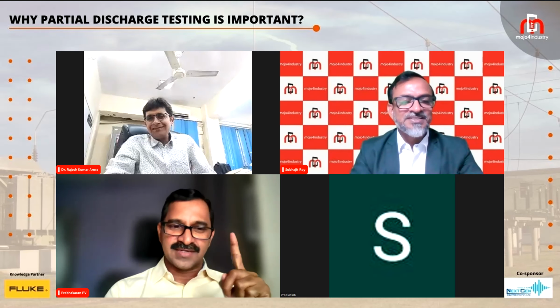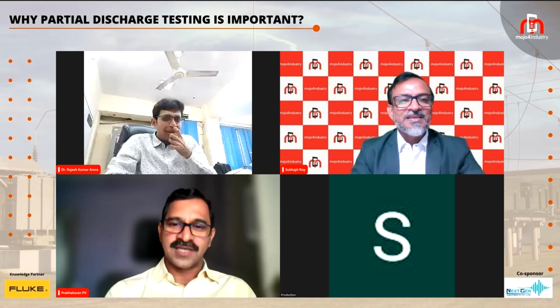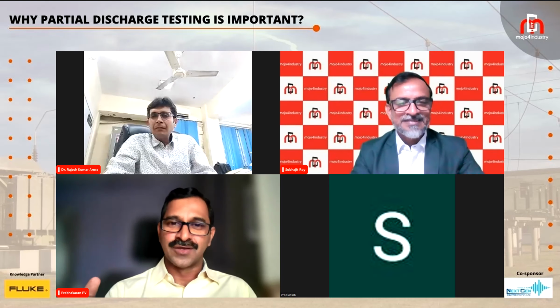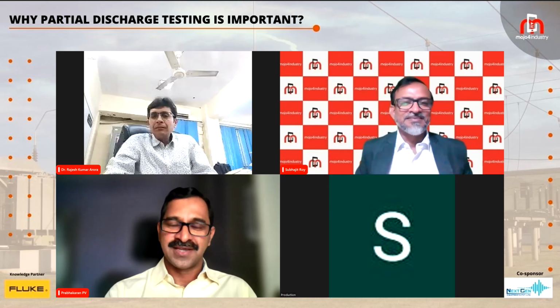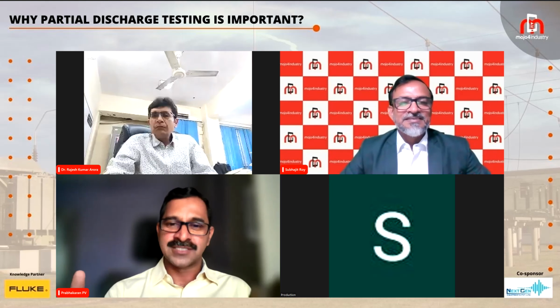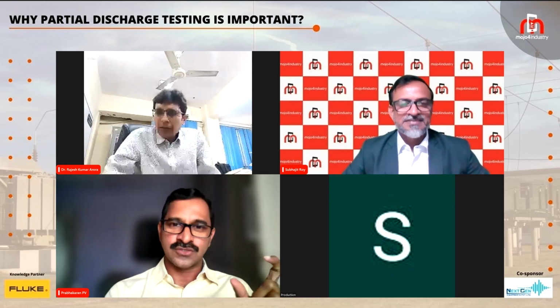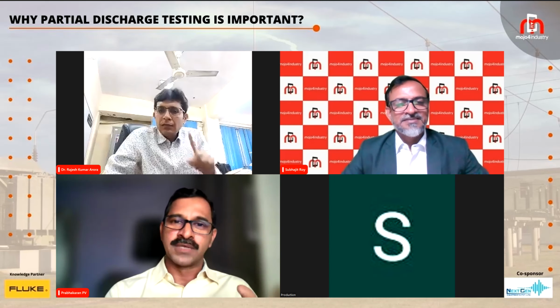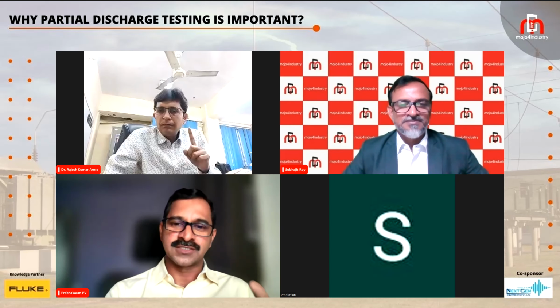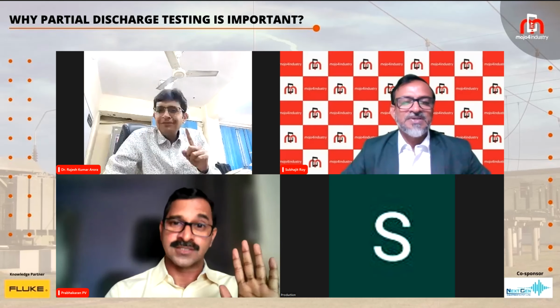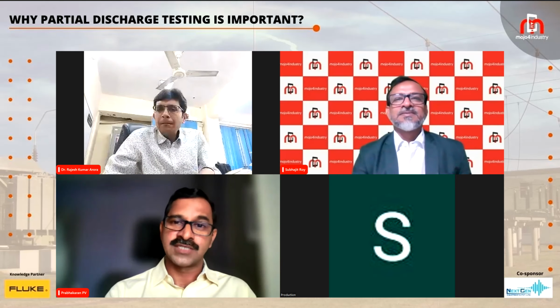Yes, Mr. Prabhakaran, you want to say something? And on top of that, what equipment are you going to replace—that is also a cost. Exactly, and when partial discharge causes a failure, the time spent restoring it is also a cost. If it's a transformer, cable, or capacitor that needs replacement, you can't repair it—once partial discharge failure or flashover occurs, nothing is left. That is covered under the availability pattern of that utility, so that's the downtime.